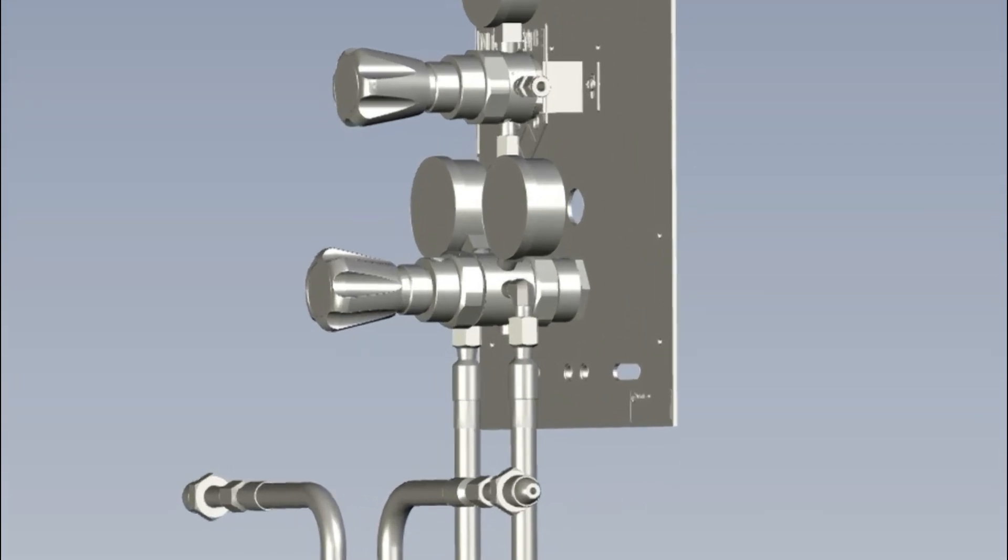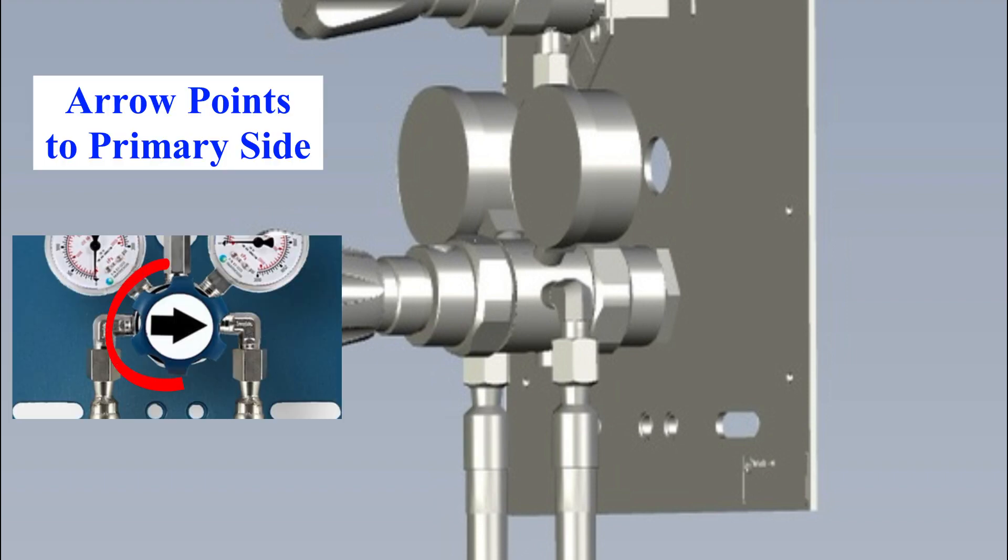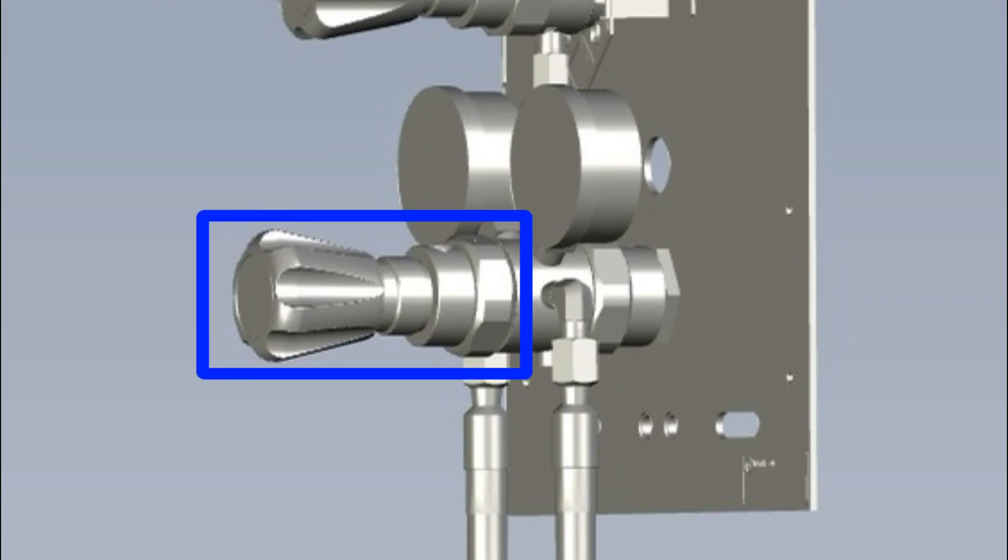The switchover regulator is actually two pressure regulators in a single body. The back regulator is preset and is for the gas source on the left side. The arrow knob is the pressure adjustment for the front pressure regulator.